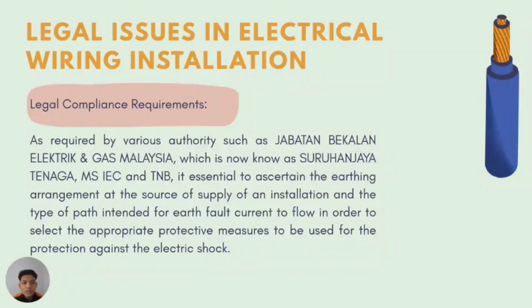Okay, next we move to legal issues in electrical wiring installation. As required by various authorities such as Jabatan Bekalan Elektrik and Gas Malaysia, which is known as Suruhanjaya Tenaga, MS IEC and TNB, it is essential to ascertain the earthing arrangement at the source of supply of an installation and the type of path intended for a fault current to flow, in order to select the appropriate protective measures to be used for the protection against electric shock.